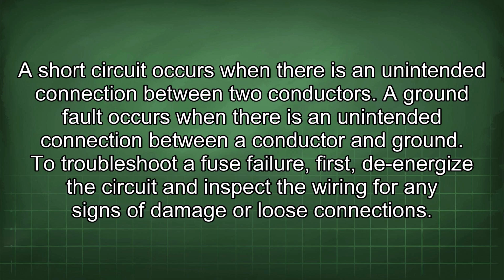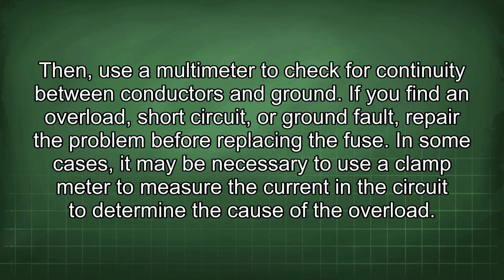To troubleshoot a fuse failure, first de-energize the circuit and inspect the wiring for any signs of damage or loose connections. Then use a multimeter to check for continuity between conductors and ground. If you find an overload, short circuit, or ground fault, repair the problem before replacing the fuse. In some cases, it may be necessary to use a clamp meter to measure the current in the circuit to determine the cause of the overload.